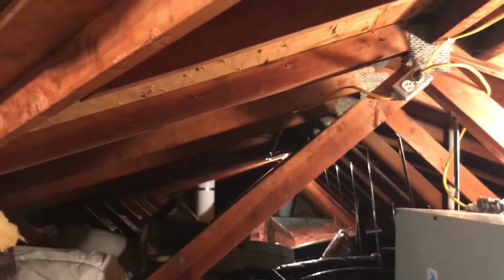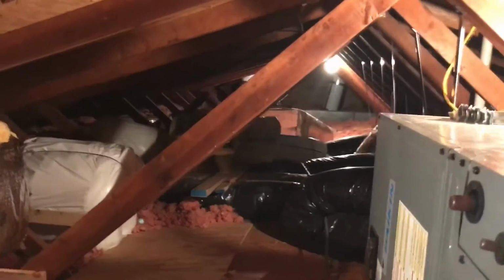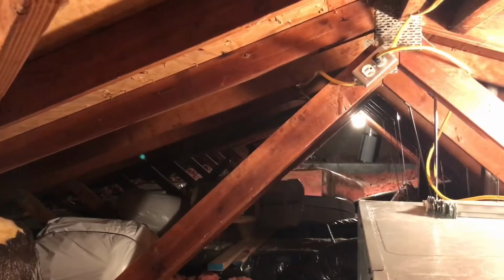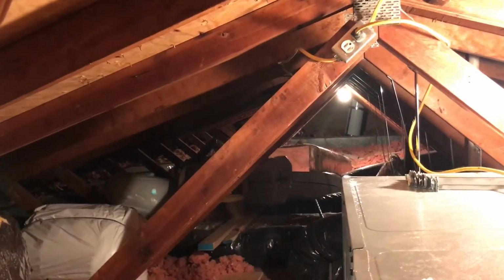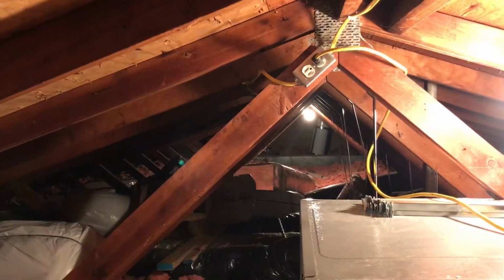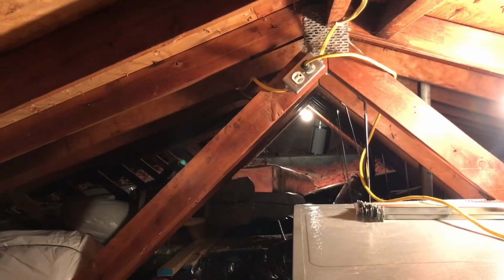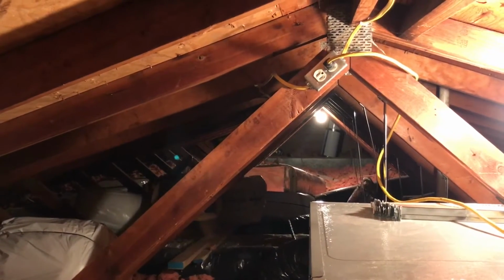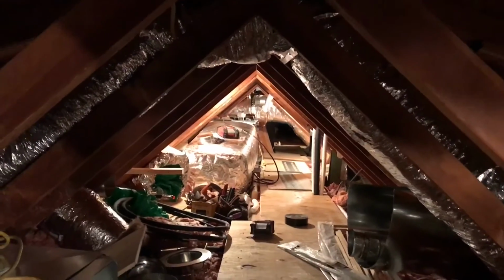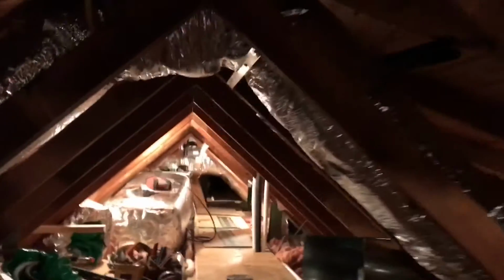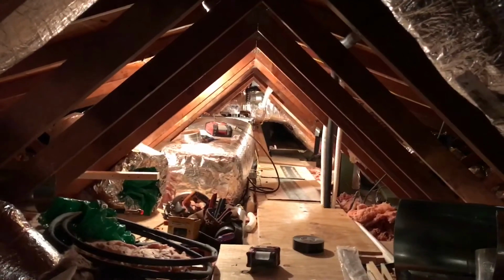So here's our other 2 air handlers, where they're going to sit. We're replacing all the ductwork in the attic. The existing is internally lined, not insulated on the outside, not sealed, and the flex duct is crap. So we're going all new, rigid trunks, R8 flex branches. We're going to reuse a lot of the register locations, upsizing or downsizing them as necessary. As you can see, we had to do some funky stuff here to get back in case we had to do some balancing. Not a lot of room up here, but I think we're making do with what we have.